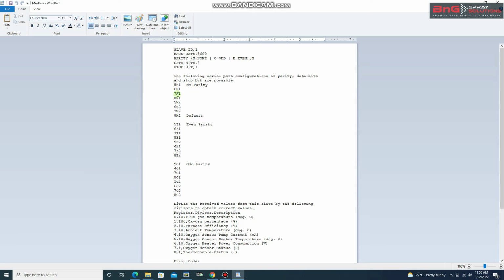The Modbus is the other file that you need to make sure that everything is as per your requirement. As you can see, there's the slave ID. So the slave ID, you put in whatever suits your system, the baud rate as well, the parity, the data bits, stop bit. So these are the things which you need to update as per your communication requirements.